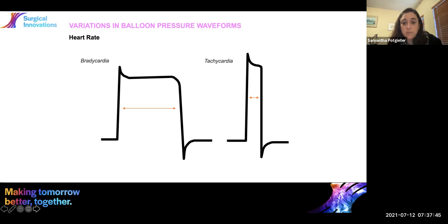The pump console uses the software that it has, and it overrides itself constantly in a tachycardia to make sure that it deflates. It focuses more on deflation than it does on inflation, because it needs to make sure that it is deflated before the onset of systole. So the pump console itself can keep up to a heart rate of 230 if it needs to, but it isn't fully supporting the patient anymore because it can't fully inflate. And that's important to note. If you're now going to just drop it down to a 1 to 2, it just means every second heartbeat is not fully inflated. It hasn't helped the patient at all. So it's important to address that and not to address the pump, address what's going on with the patient.